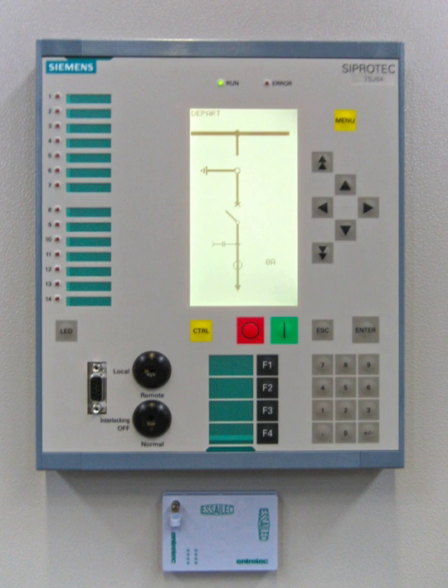They are designed for redundancy to eliminate unprotected areas. However, overlapped regions are devised to remain as small as possible such that when a fault occurs in an overlap region and the two zones which encompass the fault are isolated, the sector of the power system which is lost from service is still small despite two zones being isolated.